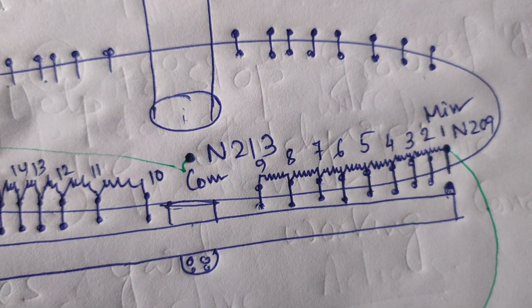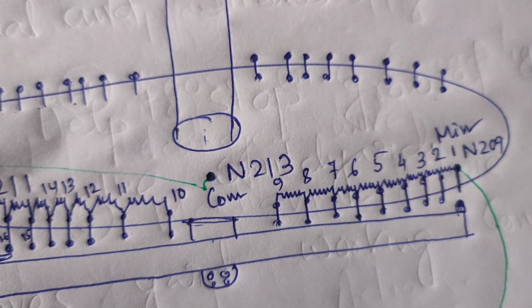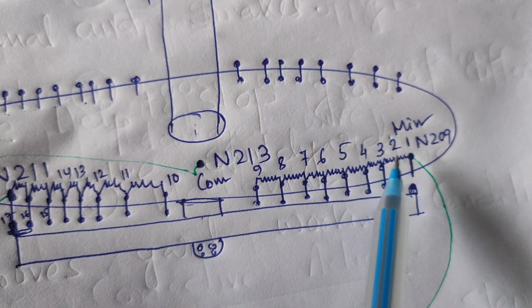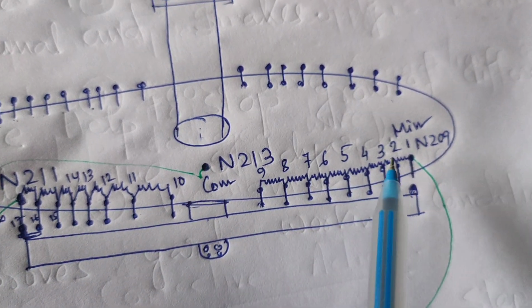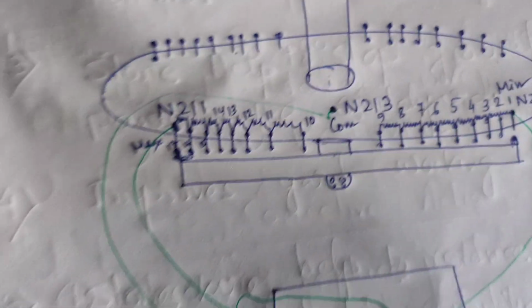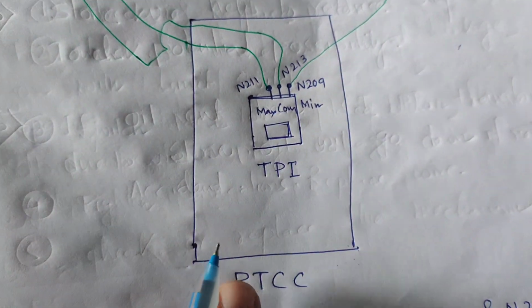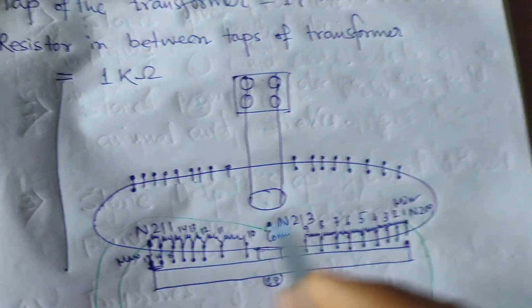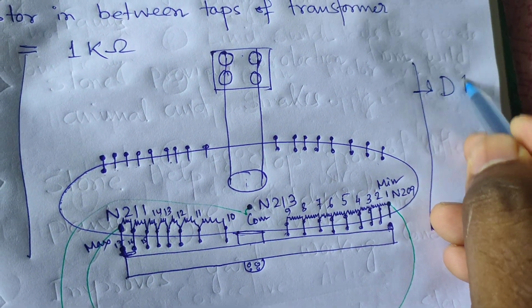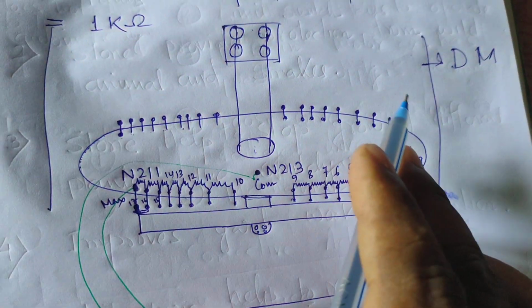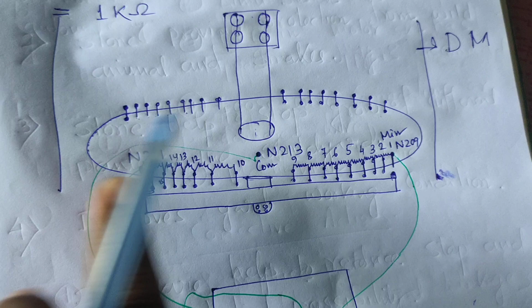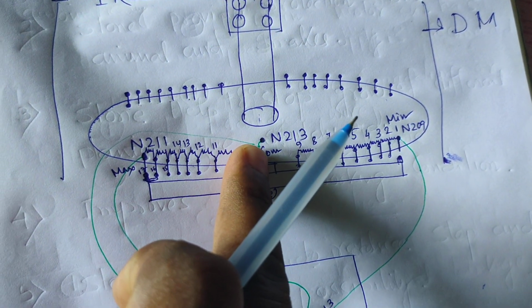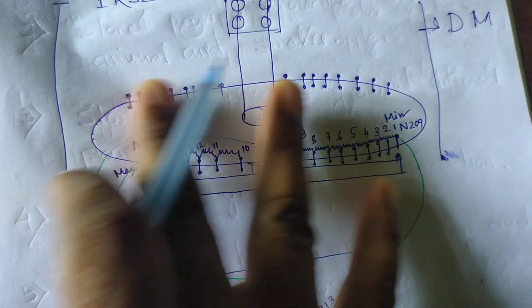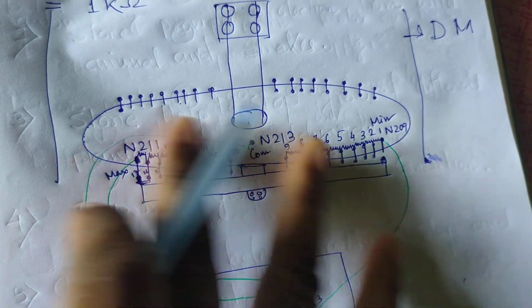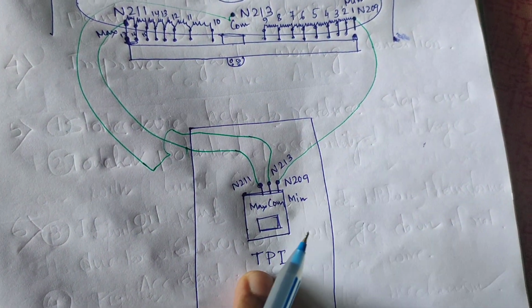If you open the DM box and look very gently, you will see the resistors connected between the tap positions, and these resistance values are converted to the TPI on the remote tap changer. This is the RTCC. It is placed inside the control building or control room, and this is inside the DM box. This is the DM box. It is attached with the power transformers, and the connections are through the control cable.